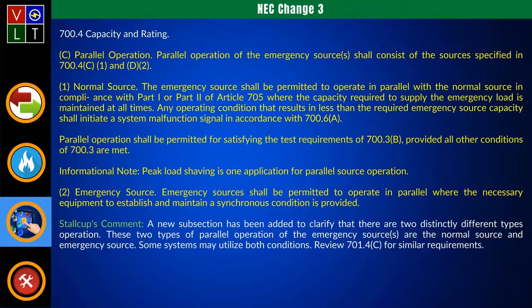So to me, there's a really big gray area that comes in here, and we'll get into this more when we get into microgrids and the 705s later on. But they say scope is under normal operation. Well, normal operation of this equipment is in an emergency. So it's weird to say that you're in an emergency situation, but then that equipment is functioning under normal operation. I think there's a little bit of work we could do with the code language to help this, because why would you tell me it's under normal operation and it's not even running? Because under normal operation, it's in an emergency condition.